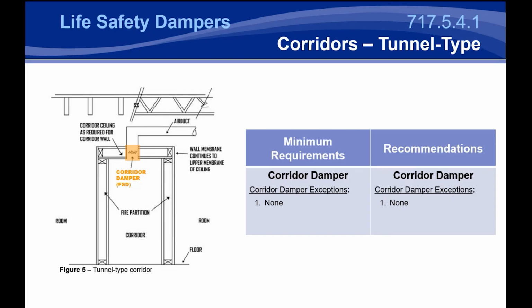Now, there are very specific fire smoke dampers that are certified as corridor dampers. They go through an additional 1 hour test to be installed in this tunnel type corridor ceiling. The pitfall that I'd like to point out is there are framing instructions for horizontal applications when you're dealing with these tunnel type corridors. Now, these are really only applicable to these tunnel type corridors. So you have to support that corridor ceiling from the bottom on both sides with the identical wall construction, and it has to form a continuous barrier up to the ceiling over to the side. Because of that, it's really for these specific applications.